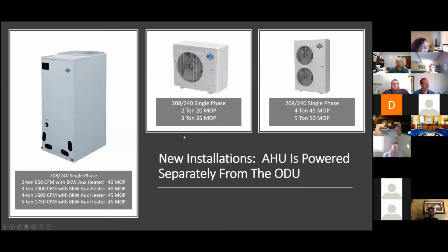Okay. So some things that are different that you've got to pay attention to. If you're doing a new residential install or a full-on replacement, we need to, and we have trim heat. So with the 8 kW trim heater, our indoor unit may need some electrical work, just something to keep in mind because we've got that heater to power up. Outdoor units are very similar to what air conditioning is, maybe some a little higher, maybe some a little bit lower, but we're not powering the heater off of the outdoor unit. So important to remember.